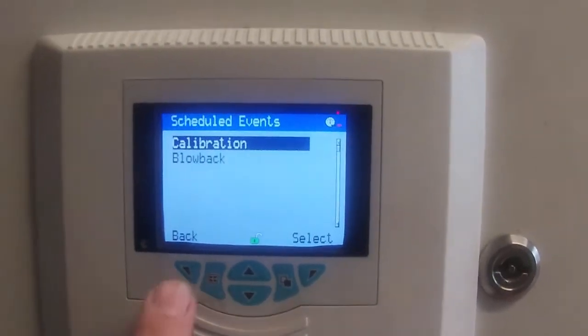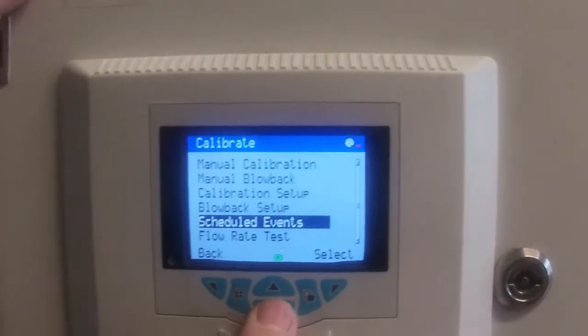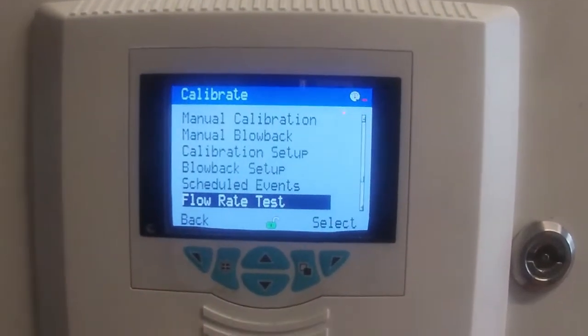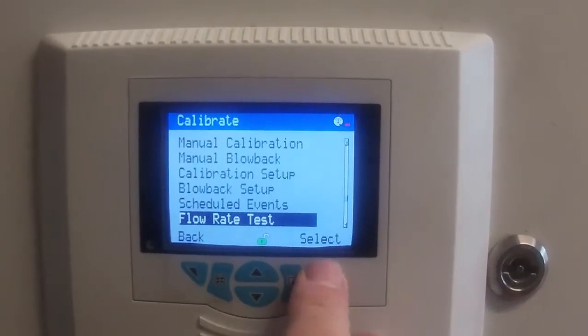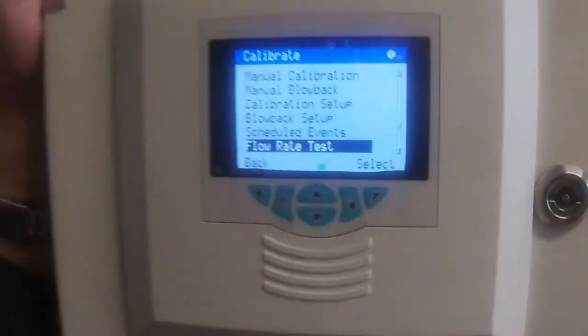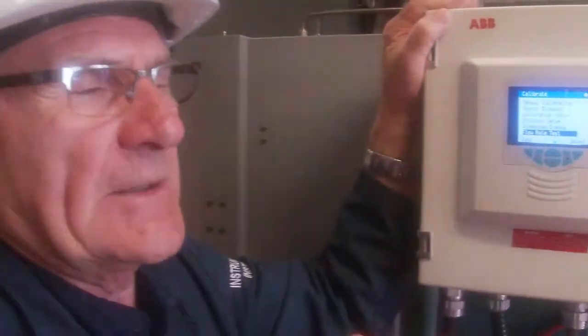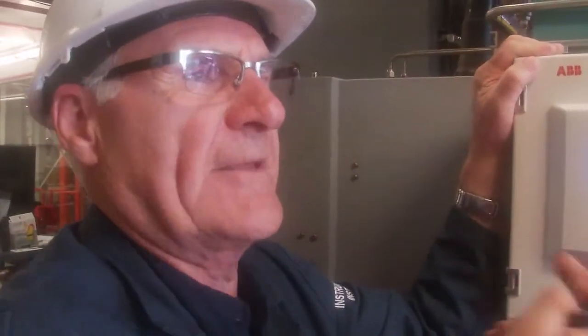They don't drip very much. Okay, flow rate test. We're going to have to go through and do one of these where we determine how much gas we need to put in there to make sure that we are overcoming what the extractor is pulling in from the flue. Basically, we'll adjust that gas flow up until the millivoltage value stops moving. When it stops moving, that means it's now seeing our gas, not what's coming from the boiler or a mixture thereof.